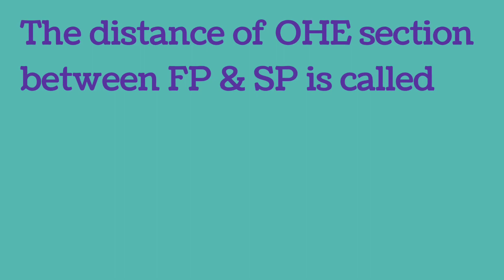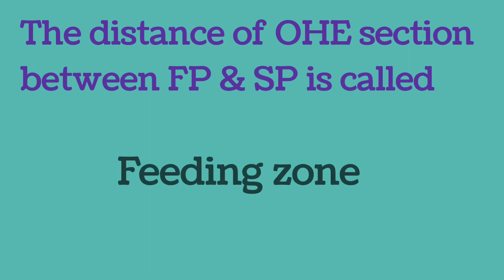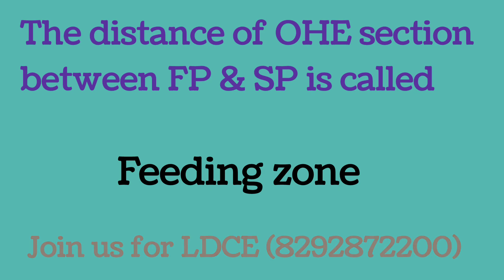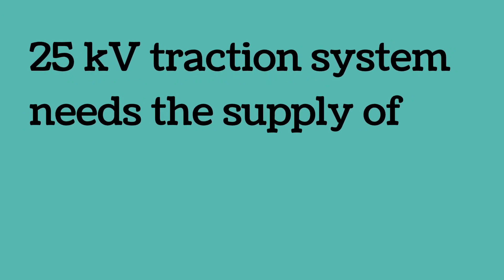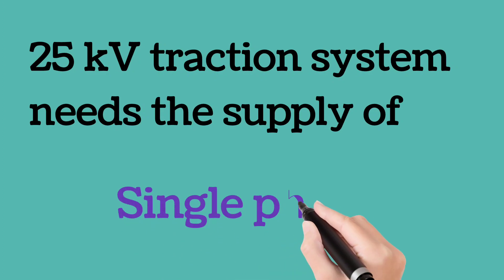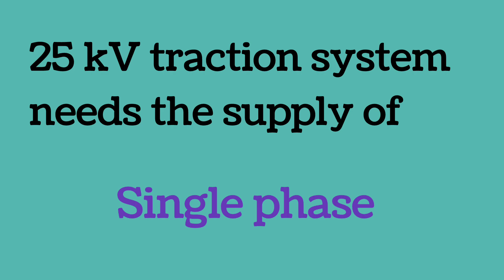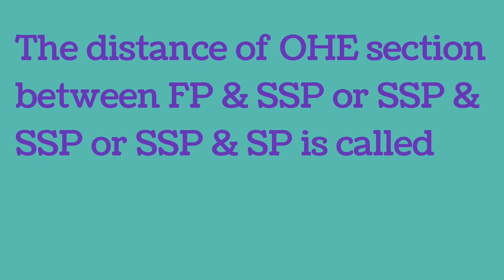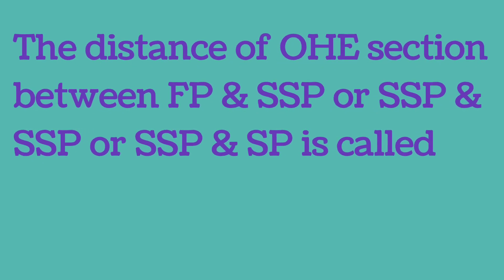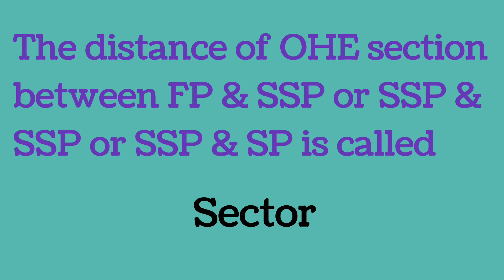The distance of OHE section between FP and SP is called a feeding zone. The 25 kV traction system needs the supply of single phase. The distance of OHE section between FP and SSP, or SSP and SSP, or SSP and SP is called a sector.